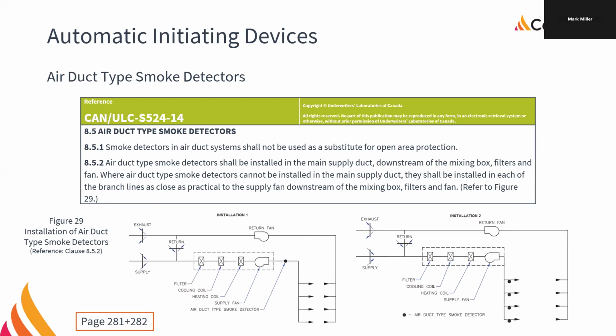Right. They've changed where they go over the years. Not all engineers have gotten that memo, because it's only been 20 plus years since they changed this. More than 20 years, because it changed before I started doing fire alarm. So it's been a very long time. We do not put duct smokes in the return air, because the return air is just coming from the area that is being served by the air handling unit, and we have area protection down there. We have heats and smokes and all that stuff in that area. So we don't care about the return air.